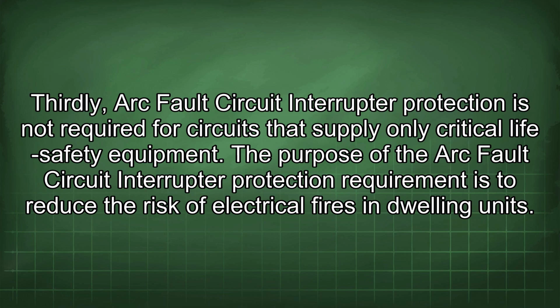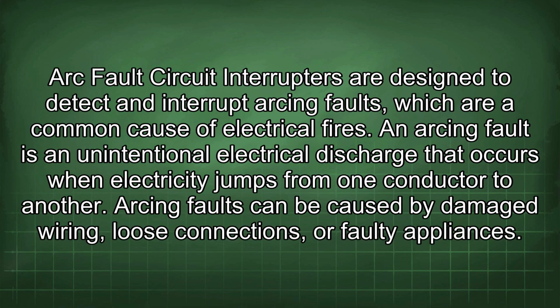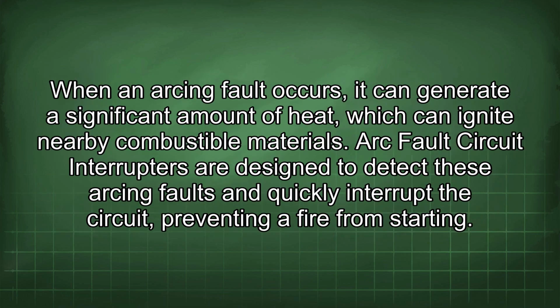The purpose of the arc fault circuit interrupter protection requirement is to reduce the risk of electrical fires in dwelling units. Arc fault circuit interrupters are designed to detect and interrupt arcing faults, which are a common cause of electrical fires. An arcing fault is an unintentional electrical discharge that occurs when electricity jumps from one conductor to another. Arcing faults can be caused by damaged wiring, loose connections, or faulty appliances. When an arcing fault occurs, it can generate a significant amount of heat, which can ignite nearby combustible materials. Arc fault circuit interrupters are designed to detect these arcing faults and quickly interrupt the circuit, preventing a fire from starting.